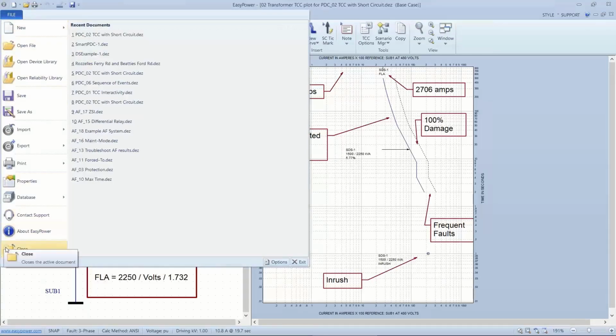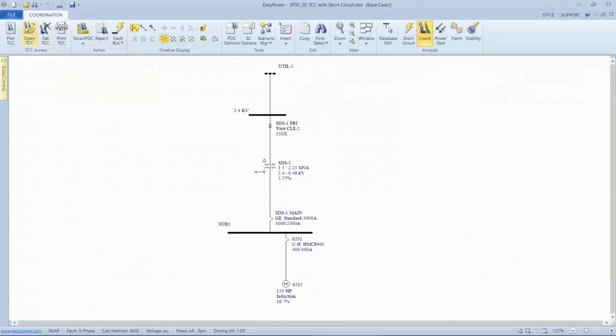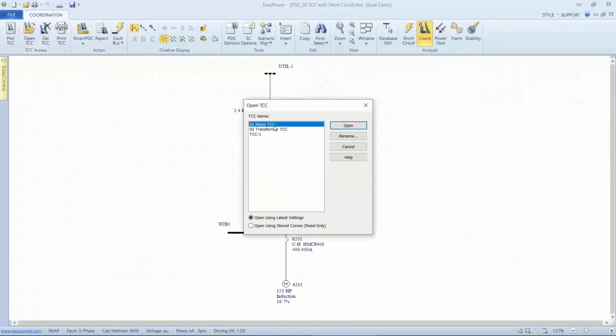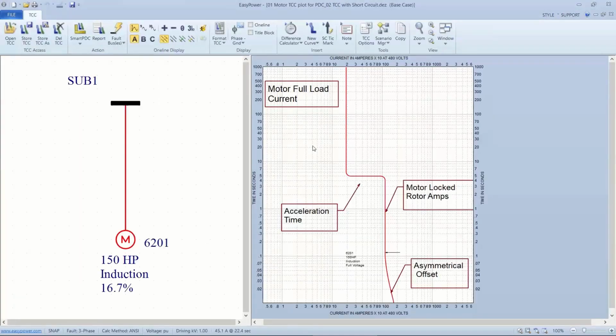So I'm going to close this TCC, and if we wanted to, we could save it. And let's look at the same setup for a motor. A motor, again, can be a relatively substantial cost to either replace or repair. And so understanding its operating region and areas that we need to either protect or not respond to are plotted based upon the parameters that were set up when we originally instantiated the motor itself.